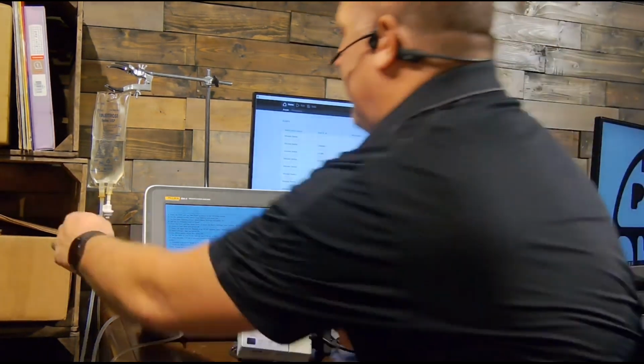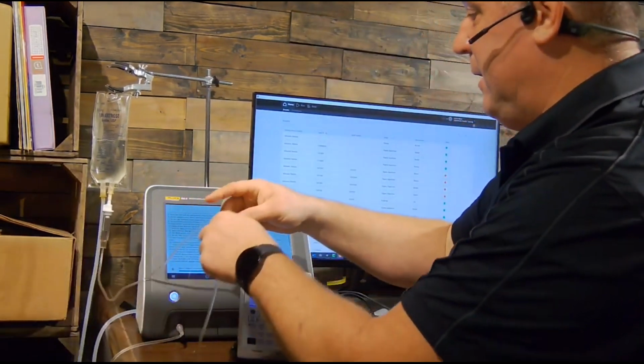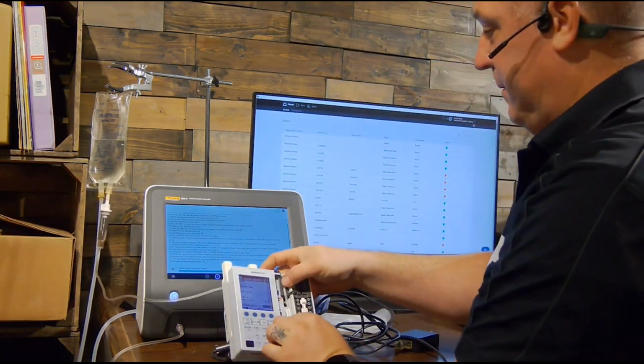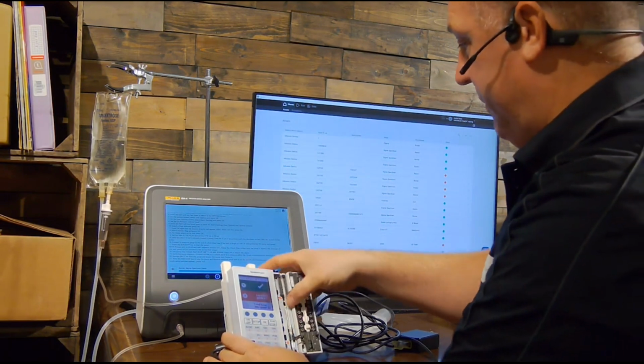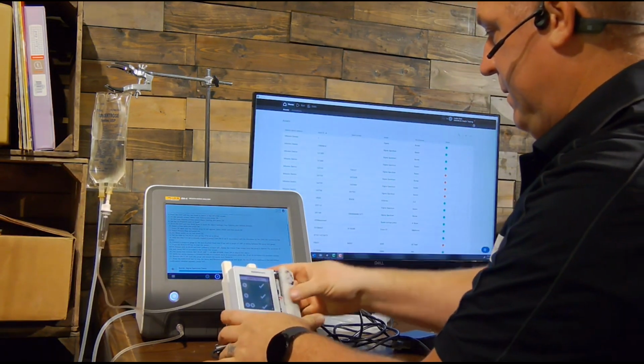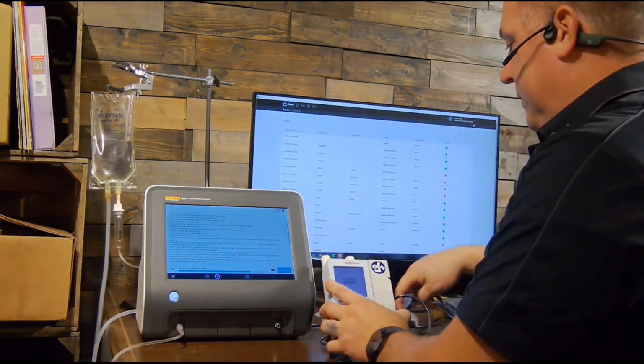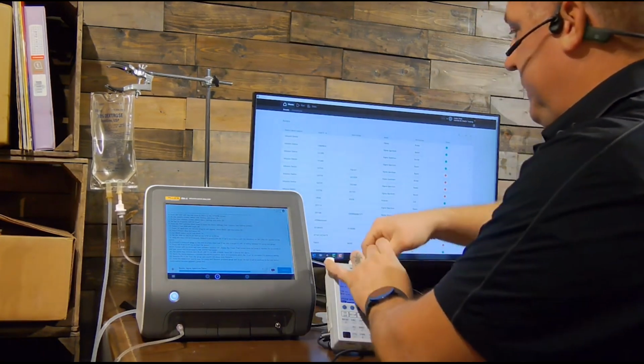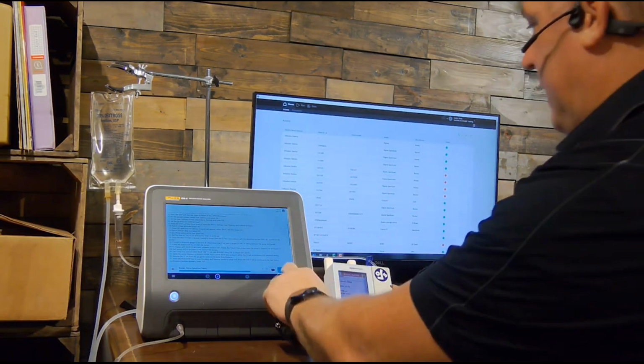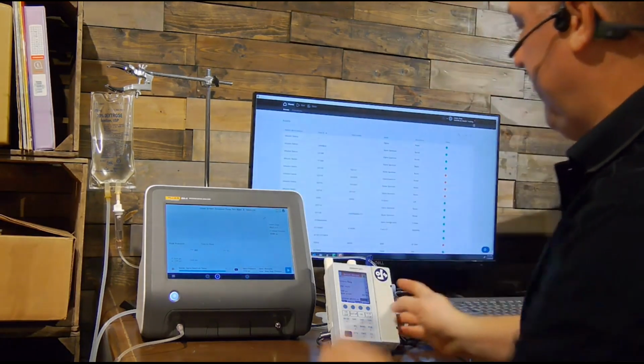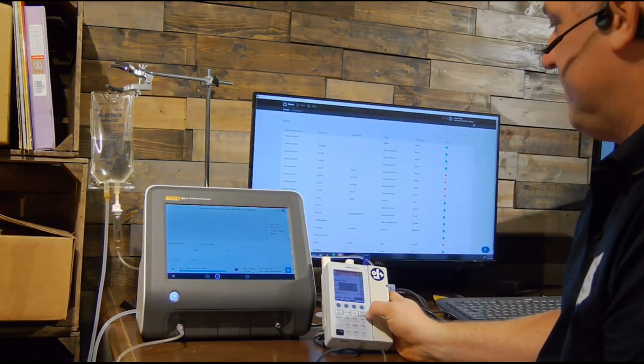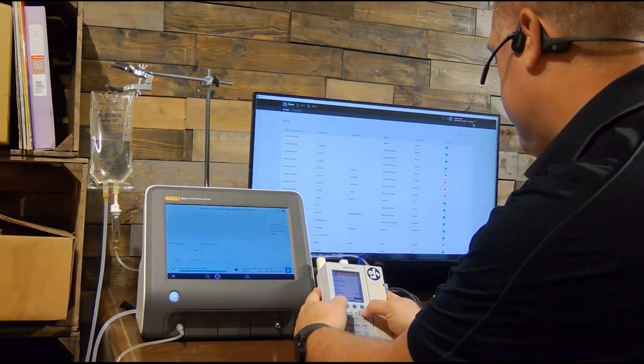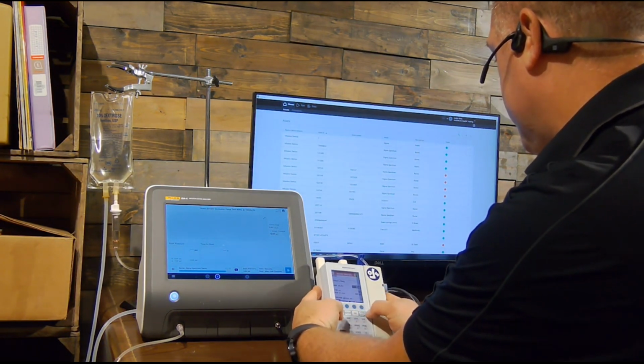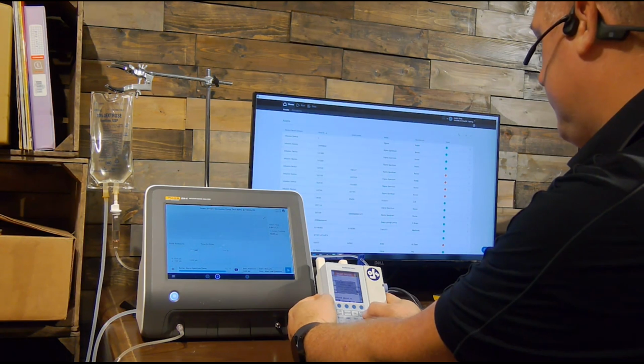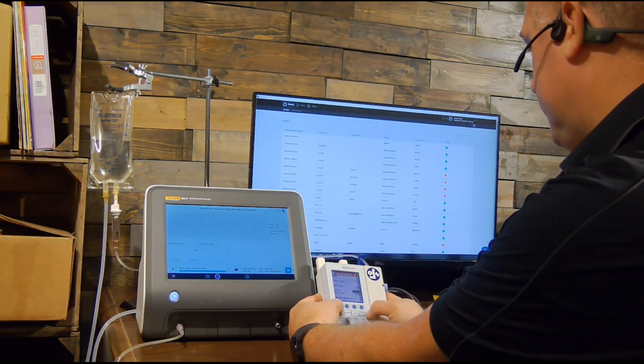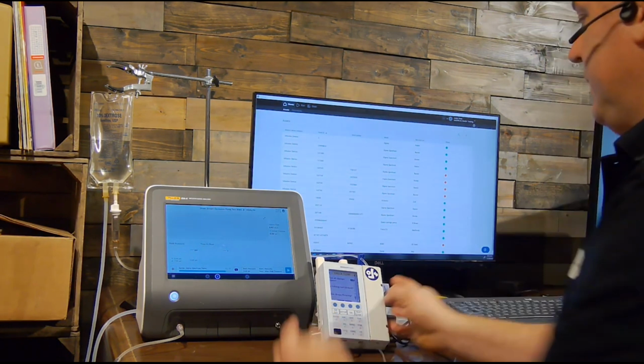All right, so now let's go ahead and we'll start this up. And I have my test set here, and we're going to talk about this test set once we get the pump running. So we'll insert this into here and continue following all the pump instructions. All right, I'll move this around. Okay, that's open. This is open. All right, now I'm going to hit continue, and I'm going to do my occlusion pressure. So I'm going to go ahead and hit run on my infusion pump. Oh, these pumps are so finicky some days. Here we go. All right.